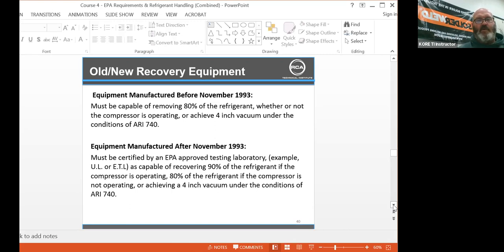Equipment manufactured before 1993, this is old and new recovery equipment, must be capable of removing 80% of the refrigerant, whether or not the compressor is operating, or achieve a 4-inch vacuum under the conditions of ARI, the Air-Conditioning and Refrigeration Institute, ARI 740. Equipment manufactured after 1993 must be certified by an EPA approved testing laboratory. Example, if a UL or ETL is capable of recovering 90% of the refrigerant if the compressor is operating, 80% of the refrigerant if the compressor is non-operating, or achieving.